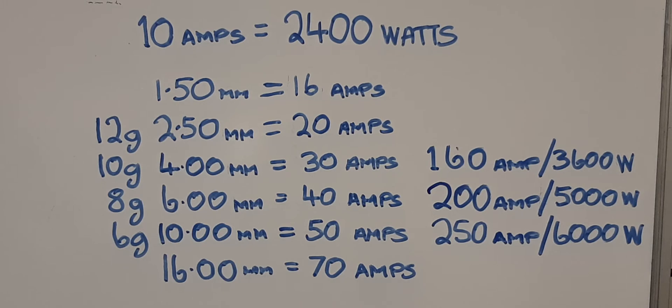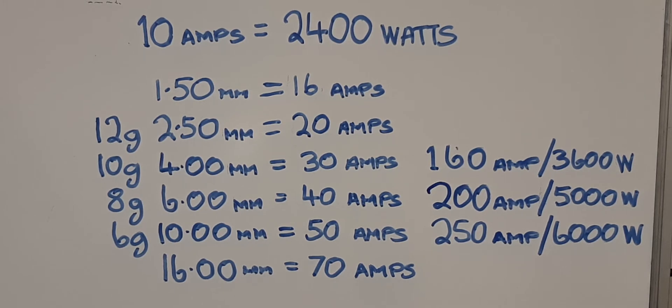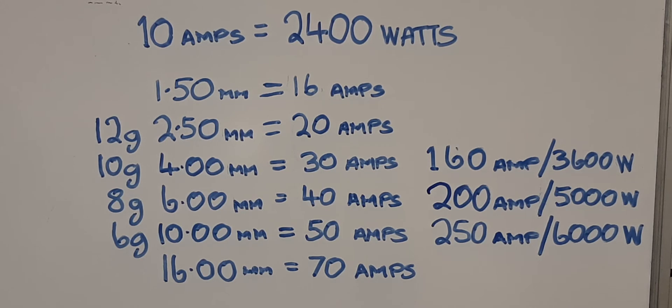Looking over to the left, I've tried to add in gauge sizes for those guys who work in gauge rather than in metric measurement. So we've got 12 gauge, 2.5, 10 gauge, 4mm, 8 gauge, 6mm, and 6 gauge, 10mm, and that's applicable to the amperage. That's the recommended amperage to draw through that size cable.